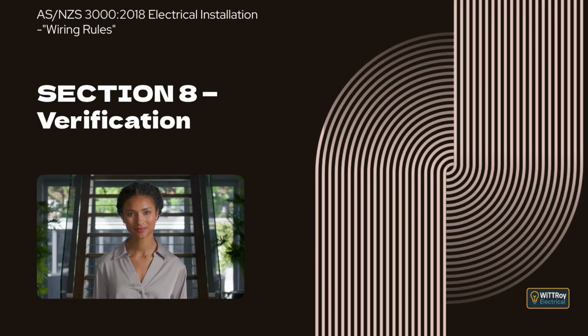Clause 8.3.7 Polarity and correct circuit connections. This clause explains that polarity and correct connection testing is carried out to prevent unsafe conditions. These include transposition of active and neutral conductors, incorrect combinations of active, neutral, and earthing connections that could energize exposed conductive parts, incorrect operation of switches or protective devices, and short circuits between conductors.